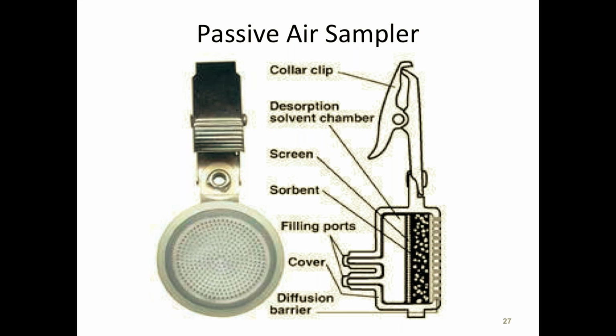And the manufacturer will have done experiments where they monitor in an environmental chamber what the level of glutaraldehyde is and what the amount that's absorbed under different conditions, temperature, and so on and so forth. They will ask you to take this device, send it back to them, give them the environmental conditions, how long you exposed it, what the temperature was, what the humidity was, and so on and so forth. And they'll report back to you and tell you that the average amount of the VOC that you're using this for is most likely at this average concentration.